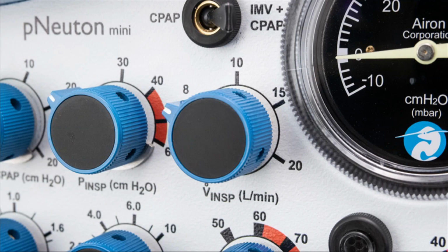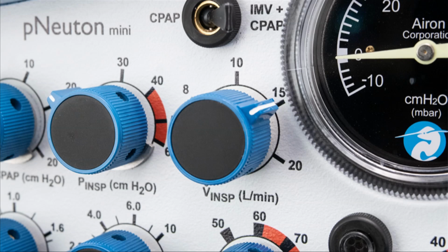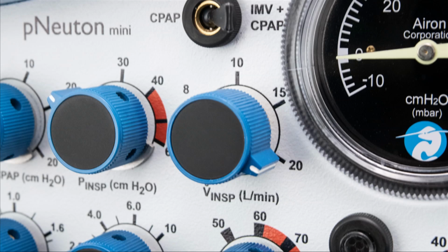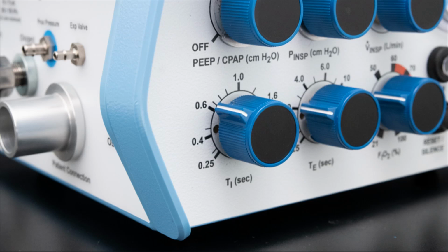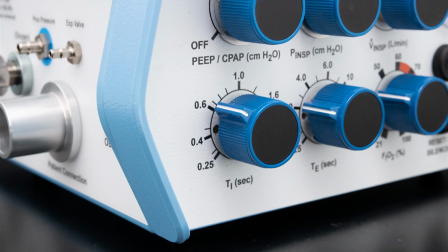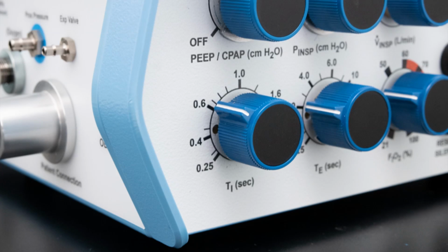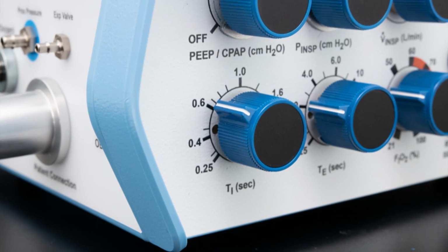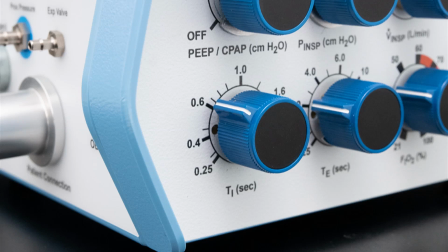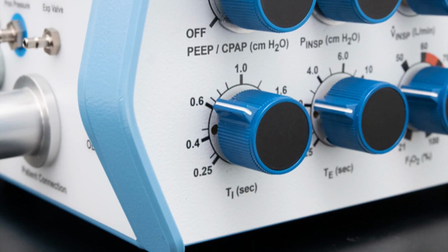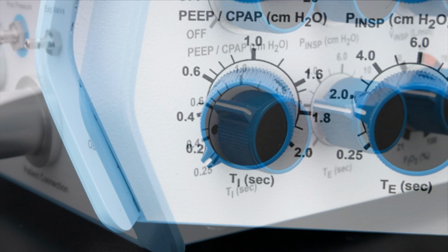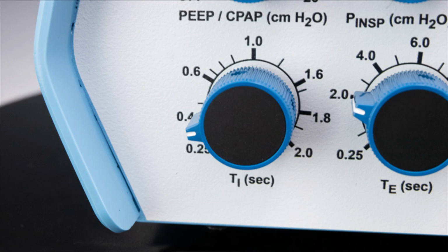When you set a specific flow, you will feel the control knob click into place. The ventilator will only deliver flow when the control is set and clicked into one of the 5 flow rate settings. Inspiratory time control. In the bottom left corner is the I-time, or inspiratory time control. This control sets the inspiratory time of mandatory breaths from 0.25 to 2 seconds and operates only in the IMV plus CPAP mode and can be used to manage tidal volume delivery. The longer the set time, the higher the tidal volume.